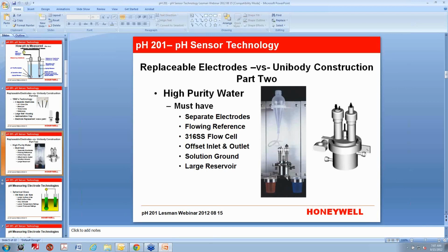You have to have a 316 stainless steel flow cell so that you can take that to a really good earth ground. The inlet and the outlet are offset so that you don't get a siphoning action off of the outlet. If you have one of these and it's siphoning, you can usually tell because it will suck up the potassium chloride faster than it should. And then, of course, we have the very large reservoir on top, which makes this an ideal sensor for measuring high purity water. And you really have to have it. You can't use something with a gel reference. You can't use the unibody construction because it just uses the KCl too fast. That's such a small volume. So you have to have this for high purity water, but it's not a very good sensor for any other application. So the replaceable electrodes are mostly used in power plants for high purity water.